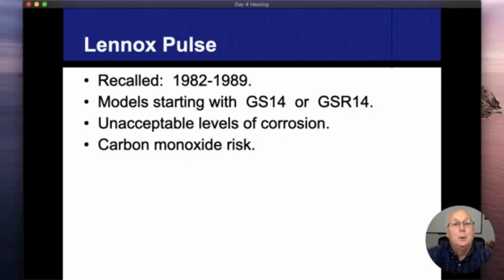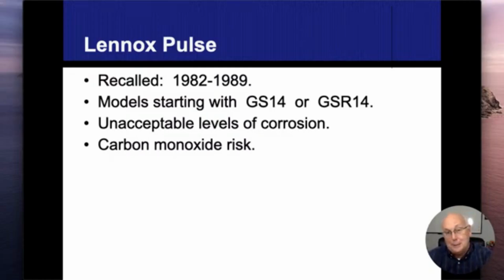So they were recalled in 82 to 89. Models starting with GS, GSR. The reason why they were recalled, because these are condensing furnaces. They are high efficiency. They did have a high level of corrosion, which damaged that secondary heat exchanger. Again, best thing you can do, look on the floor of that blower fan, see if there's any water underneath there. And as long as there's an opening there, then it pumps out carbon monoxide, because it's a higher pressure inside the heat exchanger because of that combustion that's happening there. So it's able to pump out carbon monoxide, and that's obviously a problem.